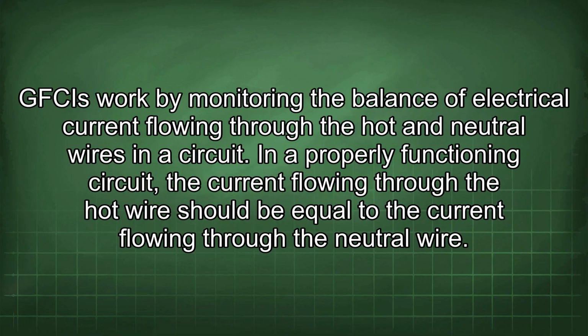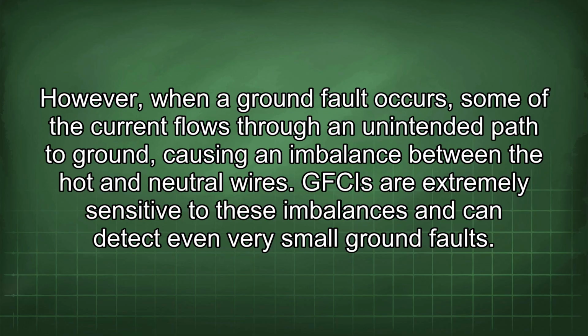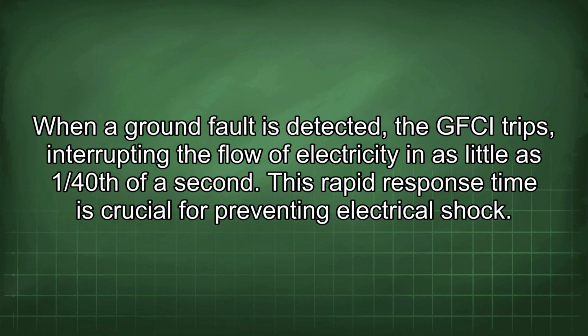GFCIs work by monitoring the balance of electrical current flowing through the hot and neutral wires in a circuit. In a properly functioning circuit, the current flowing through the hot wire should be equal to the current flowing through the neutral wire. However, when a ground fault occurs, some of the current flows through an unintended path to ground, causing an imbalance between the hot and neutral wires. GFCIs are extremely sensitive to these imbalances and can detect even very small ground faults. When a ground fault is detected, the GFCI trips, interrupting the flow of electricity in as little as 1/40th of a second. This rapid response time is crucial for preventing electrical shock.